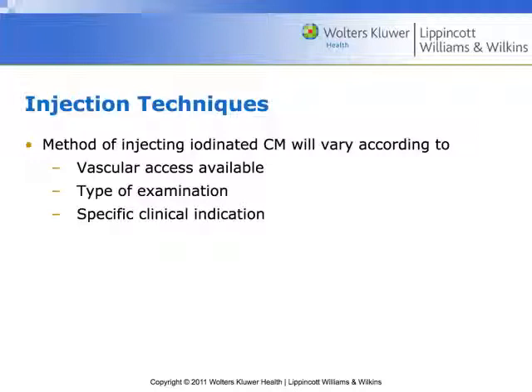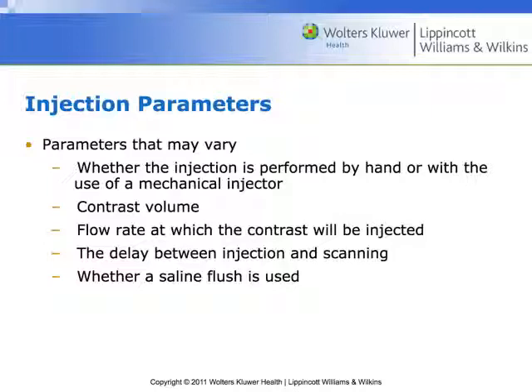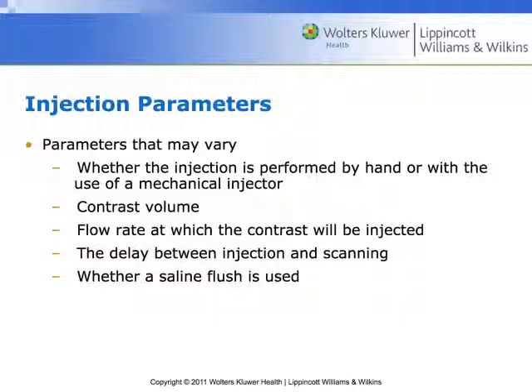These parameters for injection are going to vary. Most places I've been at, the only place where you do hand bolus injections is in the presence of a questionable access point or if you're doing pediatric imaging. Most of what we do is mechanical injections. We're going to be adjusting the contrast volume, flow rate, and a delay — meaning we're going to wait a specific amount of time before we initiate the scan, generally anywhere from about 20 to 60 seconds depending on what phase of contrast we want to see.